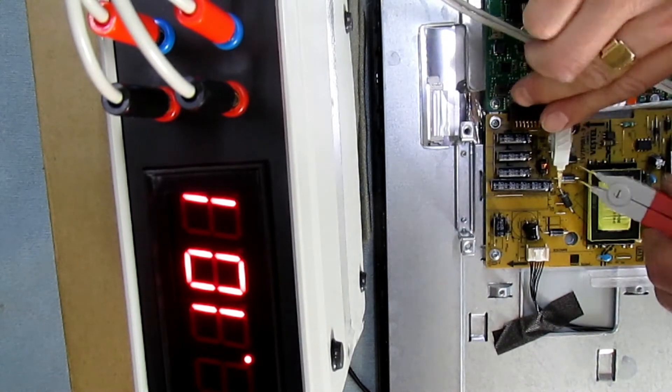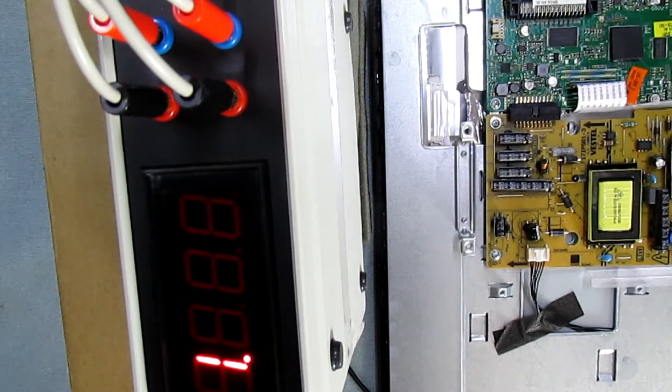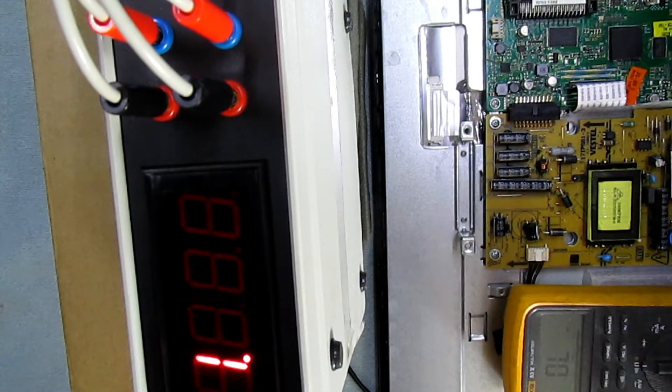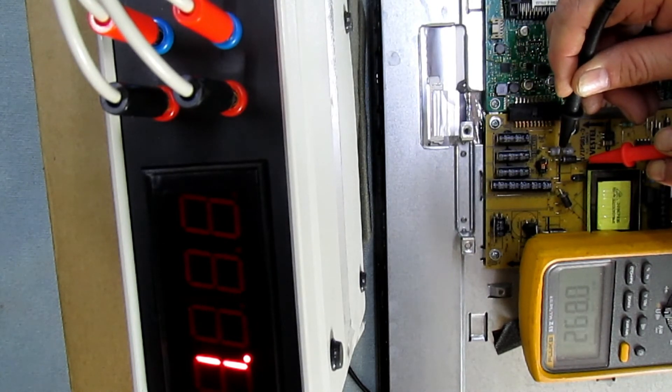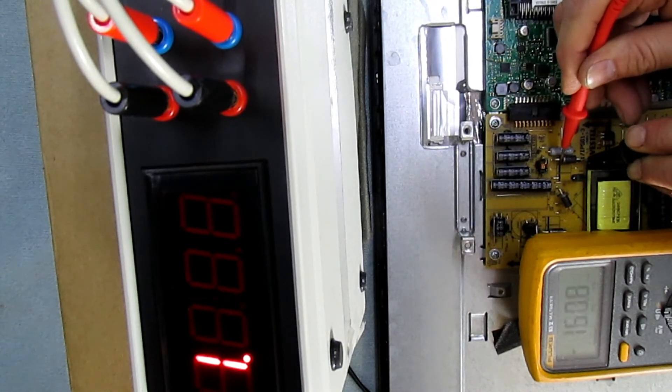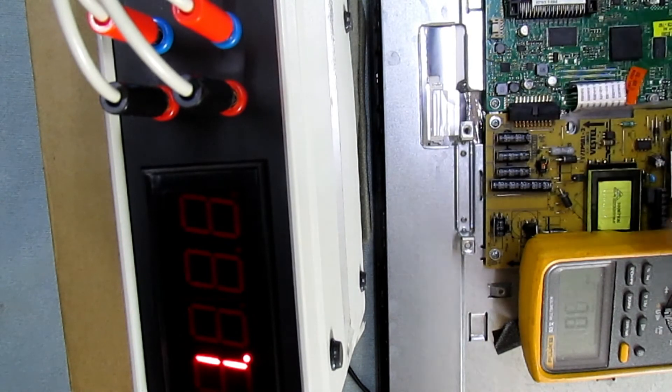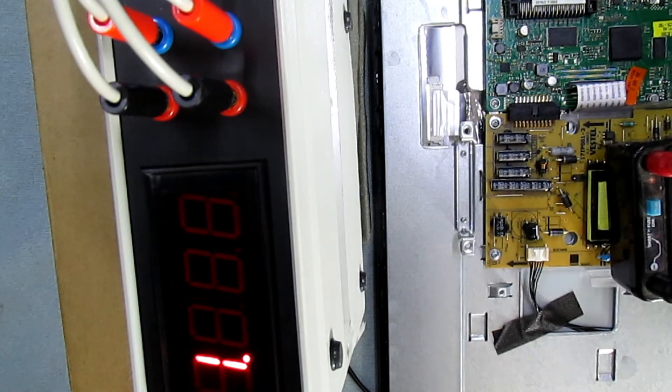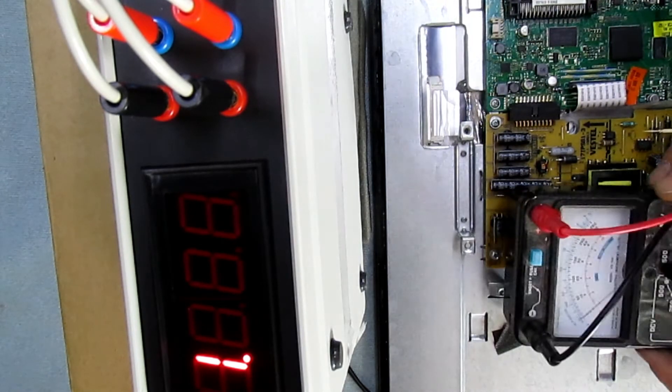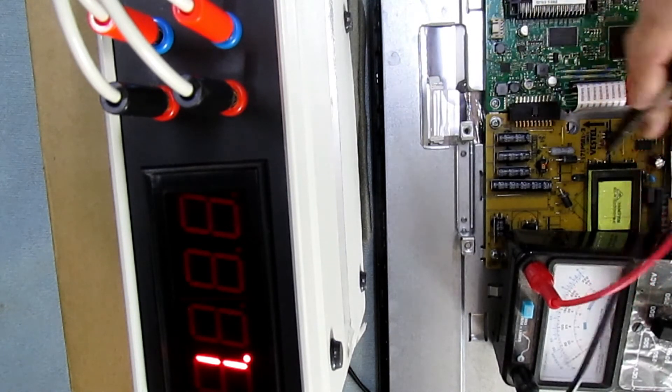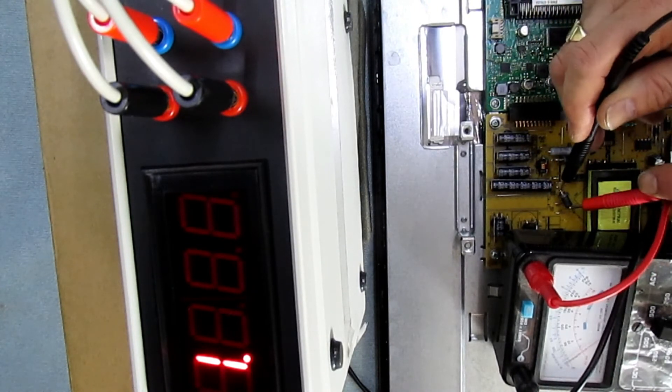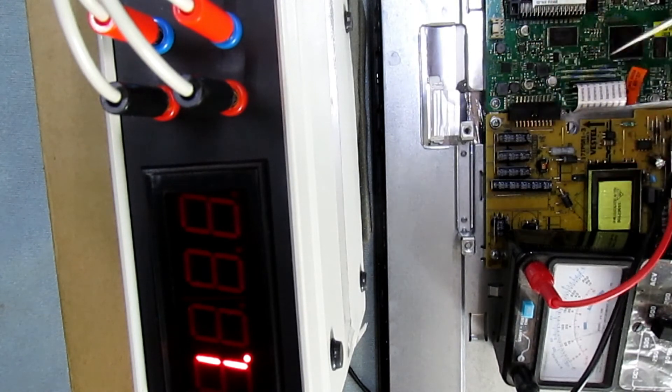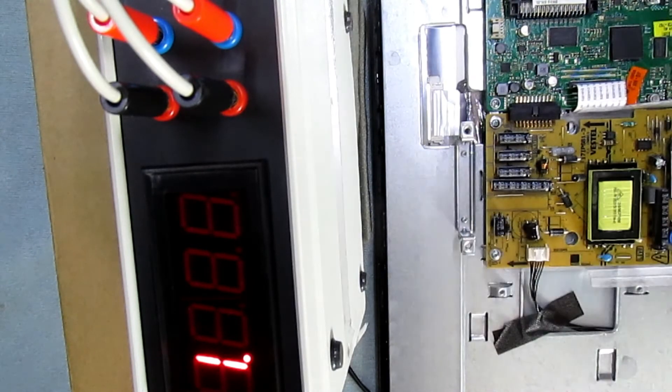So we just snip that like that to make it open circuit, measure again, there you go, short's gone. And for those who prefer to use analog meter, I'll just show you the analog meter. Make sure we've got meter in the camera there. Yep, that's the diode reading, because it's a Schottky diode, very low resistance. There you go, no short. So the milli-ohm meter again has picked out of the three diodes in parallel which is actually a faulty one.